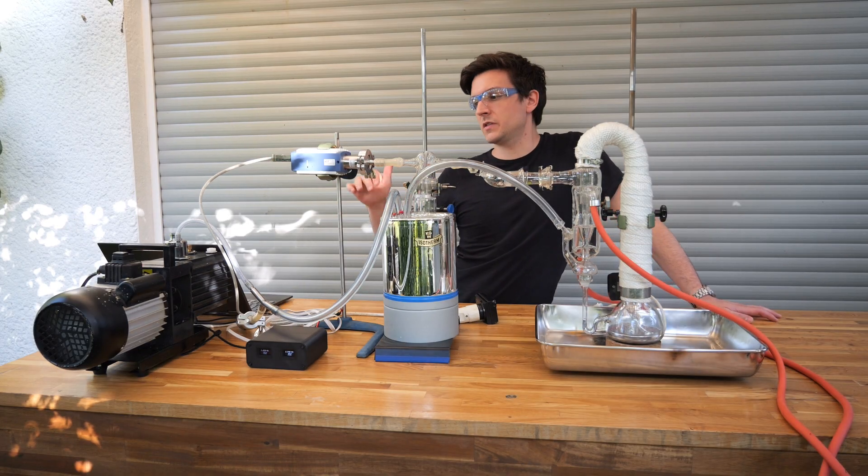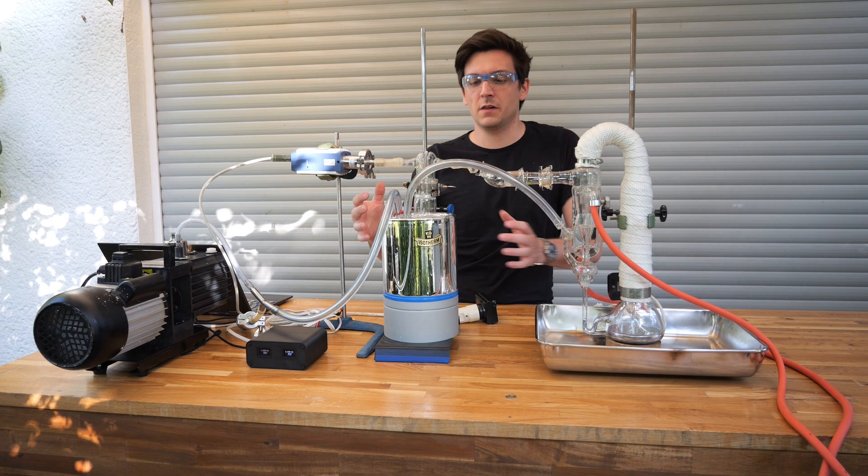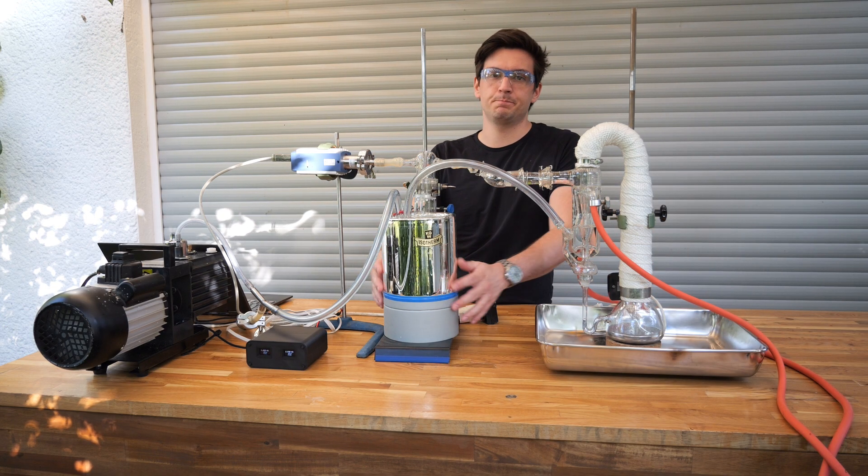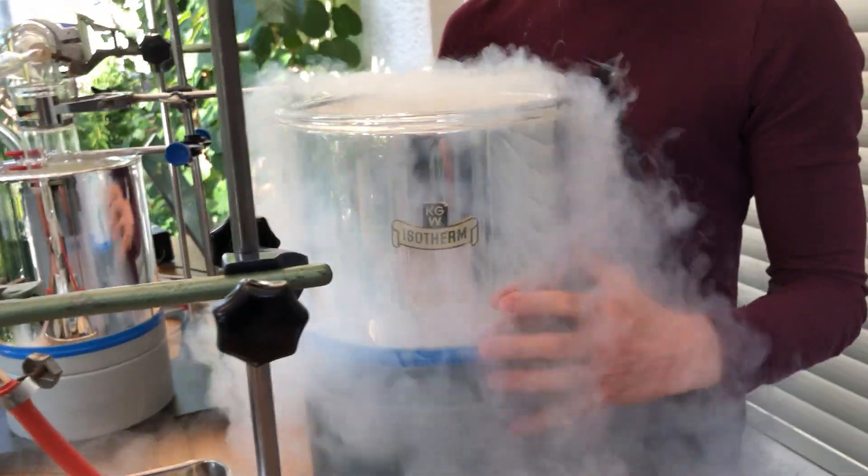So the system is almost pumped down through the roughing vacuum which means we can fill this dewar with liquid nitrogen. To fill this dewar with liquid nitrogen we are going to use its bigger brother.